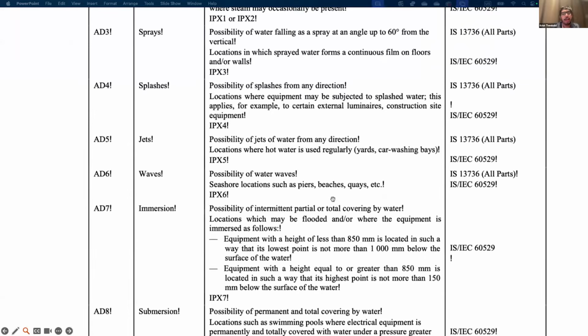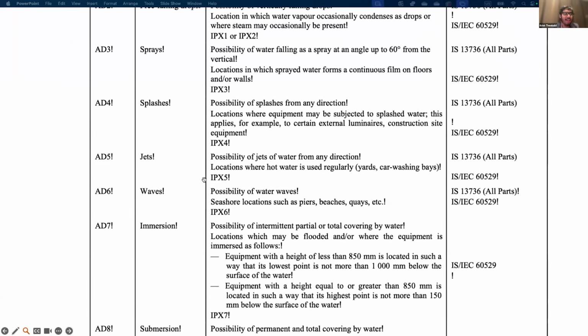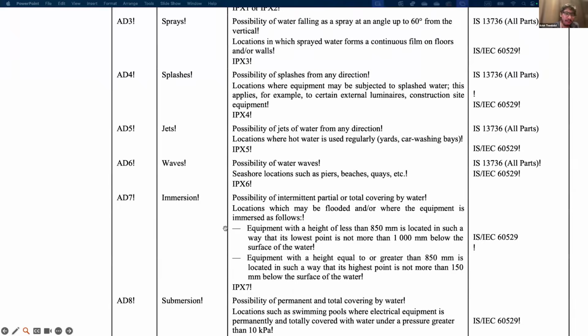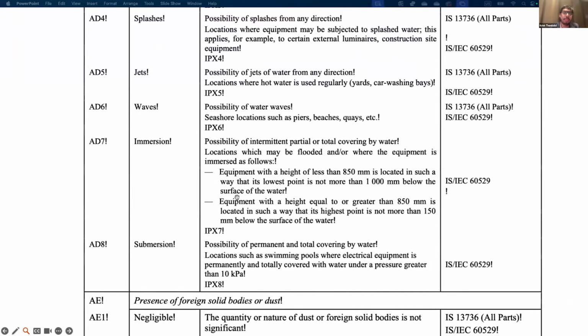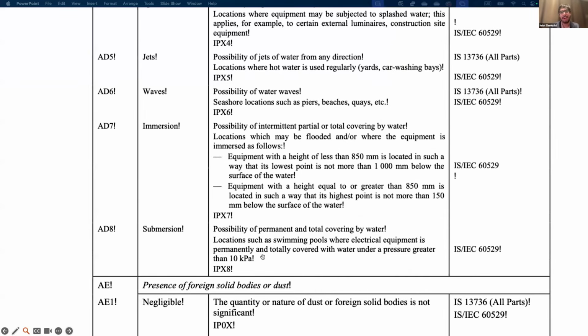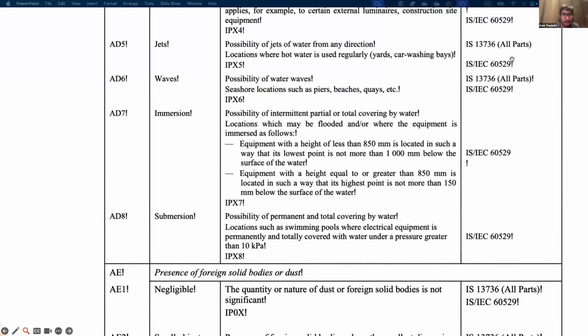See, in India, we have a problem that people just put the same equipment everywhere, and when it is installed, it is not installed correctly. But also, like Mr. Gandhi was telling me earlier, we also have a habit to over-specify sometimes, where we put IP68 everywhere, which is also completely not required. So we need to study it on a case-by-case basis. For example, last week I was in a hotel somewhere, and inside the bathroom, there was an IP66 socket. Firstly, the socket should not be inside the bathroom, and then it was in a dry area, and why was there an IP66 socket there, god knows. So very funny things that we have happening. Over-specification is a problem, and using the same product everywhere is also a problem.